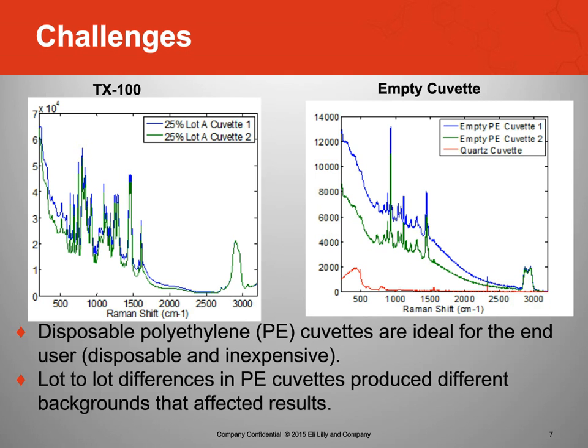And in that case, we had to figure out a way to minimize the background differences between the different cuvettes that we were using that were polyethylene. We decided to take a look at quartz. The challenge with quartz, obviously, is the user would have to clean them on a regular basis, and they're not disposable, or they could be, but it'd be expensive, similar to what we would have with polyethylene. The polyethylene was such that there's enough lot-to-lot differences between the cuvettes that we talked to the engineer and discussed the options that we had, and they felt it was more appropriate to go with a quartz cuvette and clean them on a regular basis.